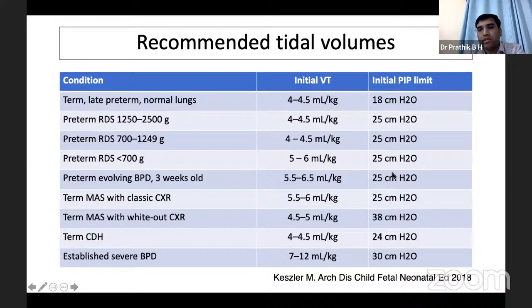Once the targeted tidal volume has been set, the next step is to set the peak inspiratory pressure. Here, the clinician is not setting the peak inspiratory pressure, but is setting the limit within which the peak inspiratory pressure is delivered. So the peak inspiratory pressure limit should usually be 3 to 5 centimeters above the expected PIP for that baby.